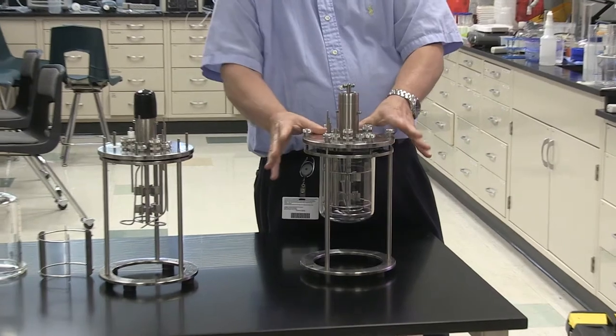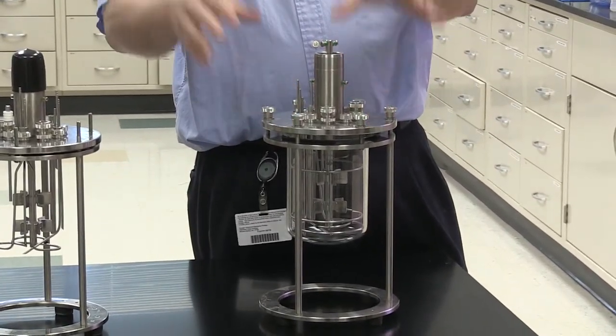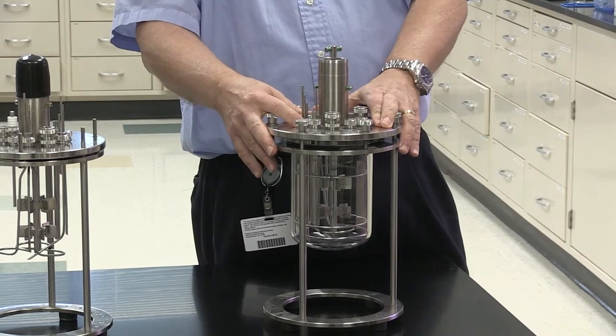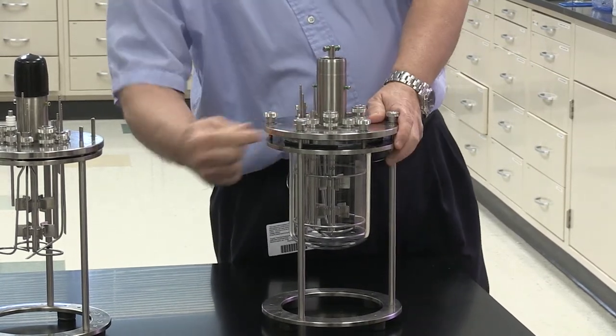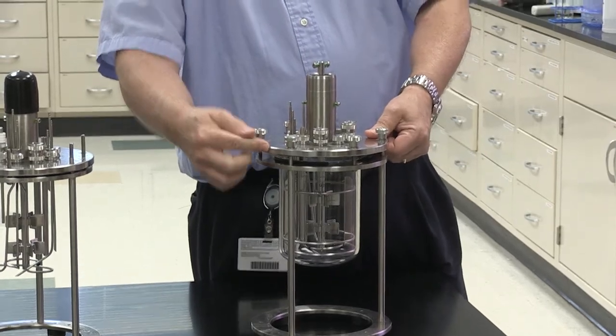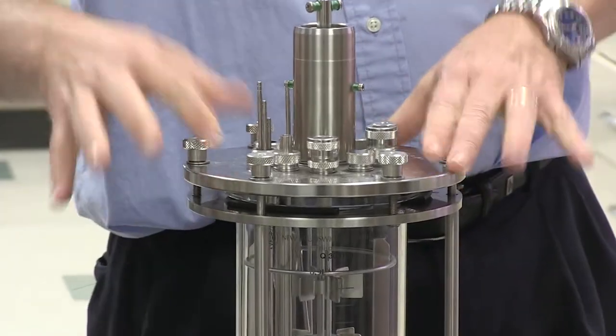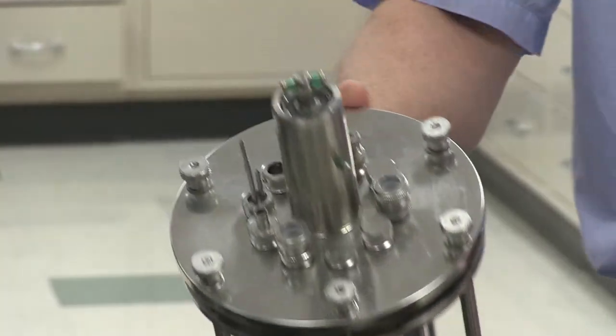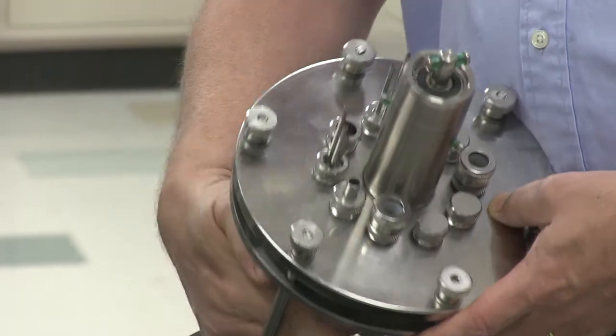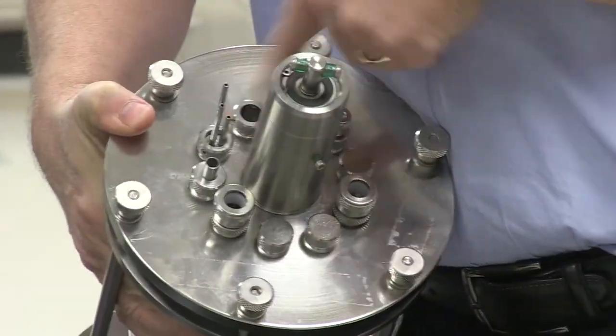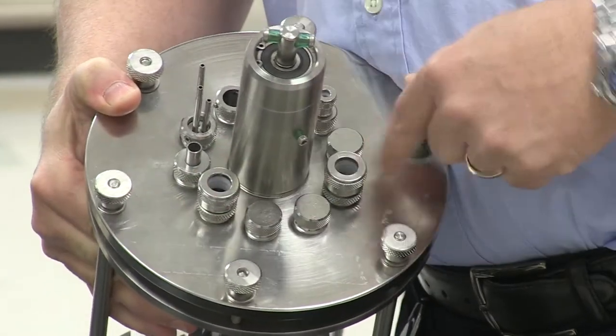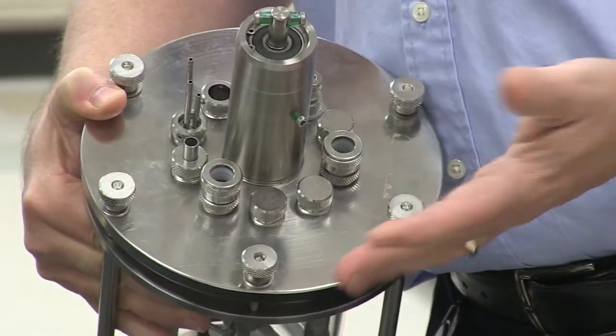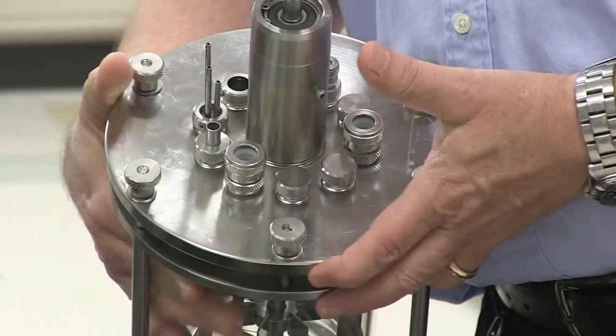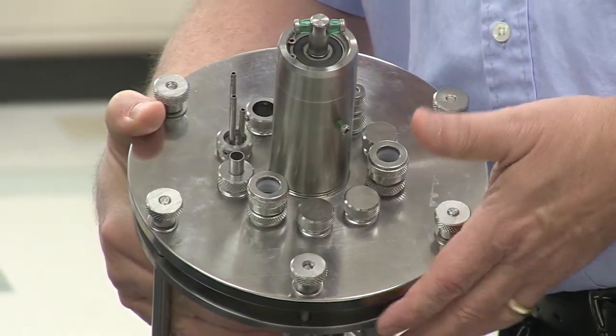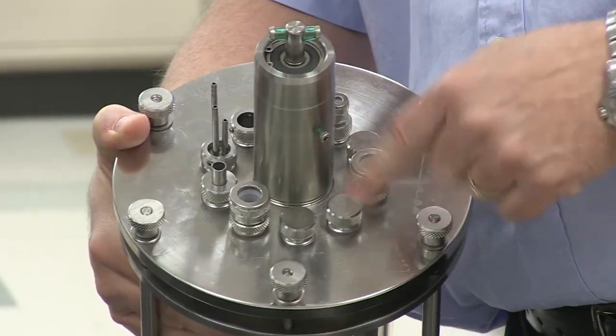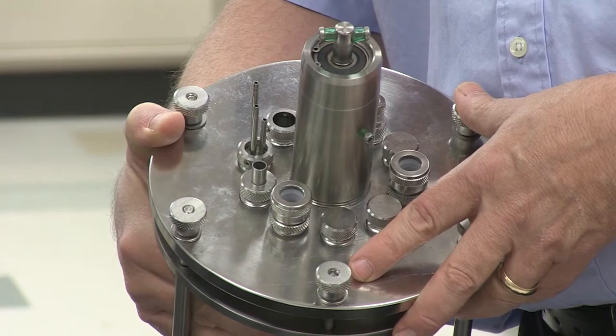And we've talked about the control loops and all the monitoring and potential additions to the fermenter. And this happens through the head plate. So the head plate is this top heavy stainless steel piece here that has all these fittings on top. And this is a typical arrangement of the head plate. Now, all these fittings are removable so that they can be placed in whatever is the optimal position for the type of fermentation you're going to be operating. This is how this particular vessel is set up for the green fluorescent protein expression that we're using.